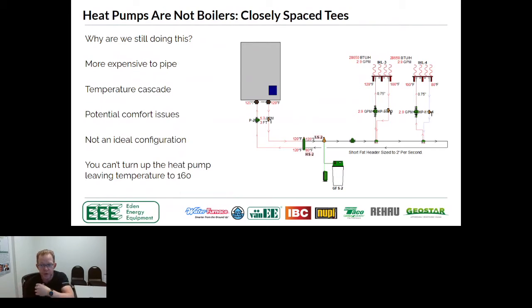Well, I have firsthand experience where people have done what you see in this drawing on hydronic heat pumps, and they'll put 9 or 10 sets of closely spaced tees, and the complaint will be the first 3 sets of tees, they have heat. The second set of 3 tees are like, we're getting degrading heat. It's not heating as well as it should. So this really isn't ideal. It's not a matter of right or wrong.